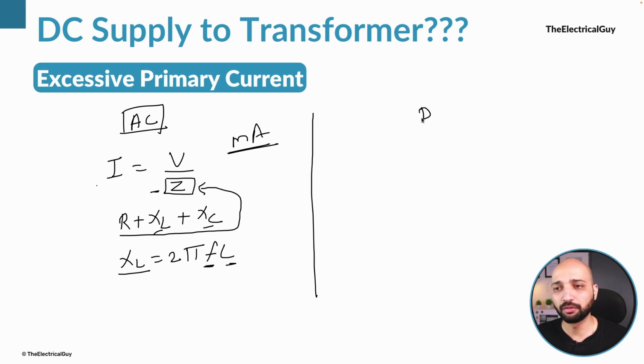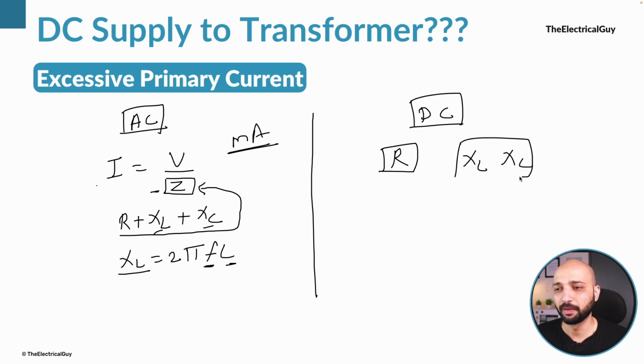The second situation, when we connected a DC supply to the transformer. Now, in DC supply, the only parameter that comes into picture is resistance, right? Since there is no frequency, there won't be any inductive reactance or there won't be any capacitive reactance. So these two things will not be there in case of DC supply. So the only opposition that current will have is resistance.